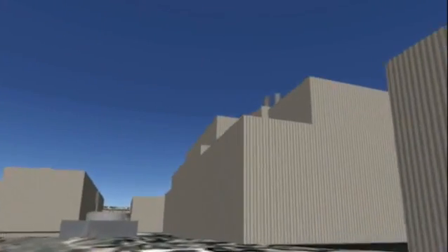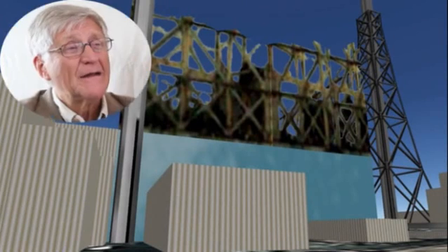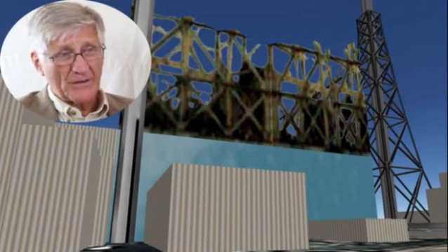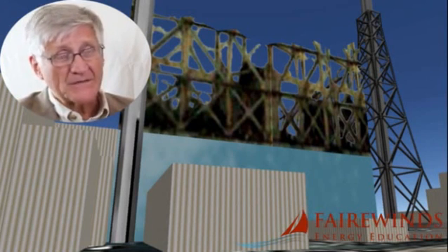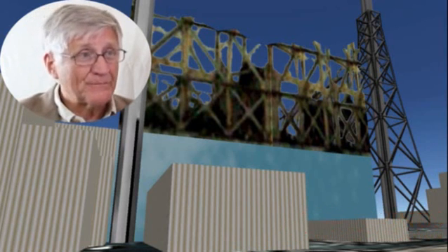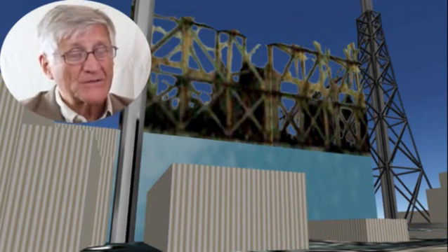What made Daiichi 4 dangerous was the fact that all of the nuclear fuel wasn't in the containment. All of the nuclear fuel was in the fuel pool. So this was the biggest concern of all the experts after the accident. And it's the reason that the Americans evacuated out to 50 miles. So even though we had explosions in Unit 1 and Unit 2 and Unit 3, that was not the big threat to the population in Japan.